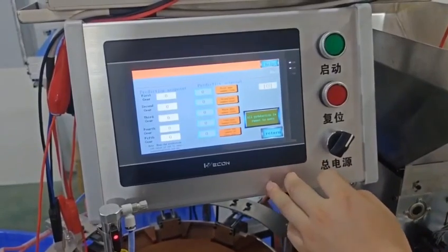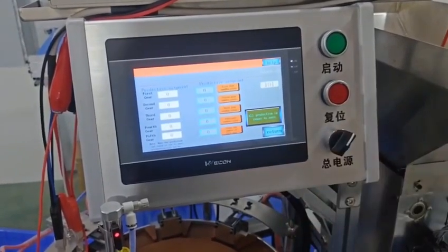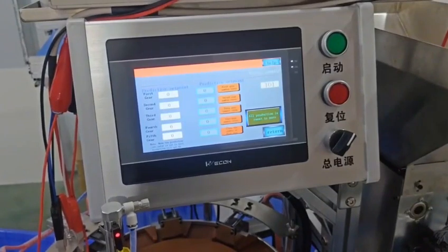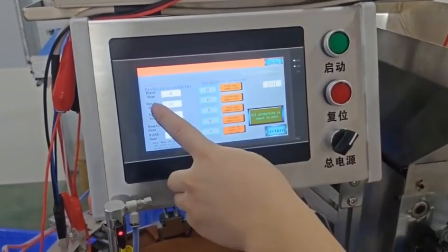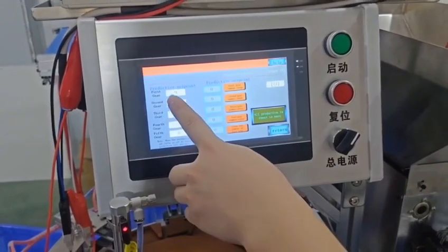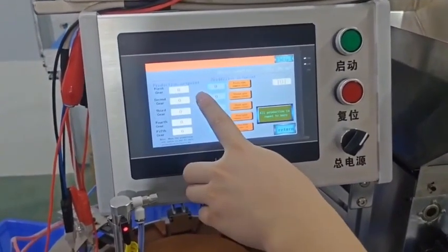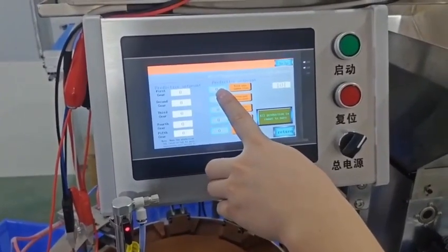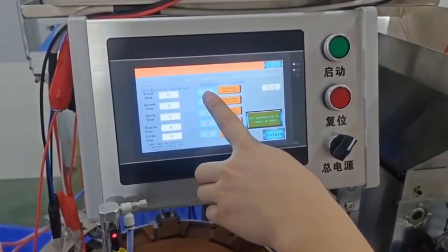Here's the horizontal conveyor belt before testing. We have 3 fiber optic amplifiers. This corresponds to our discharge sensor, a fiber optic sensor. This is the one we use to detect positioning. Compare this to our fiber optic amplifier. When there's a signal from this product, it lights up.